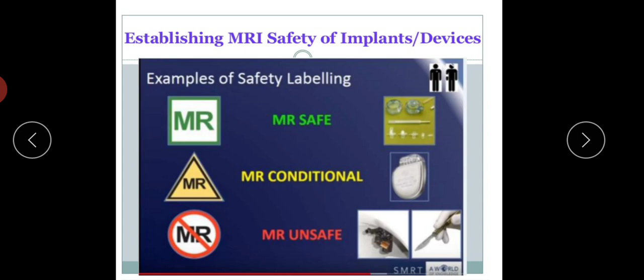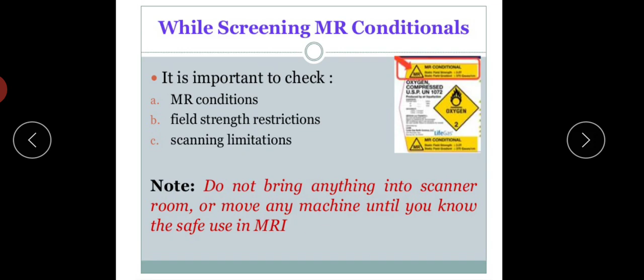Here are the safety labelings for MR safe, MR conditional, and MR unsafe. While screening MR conditionals, it is important to check MR conditions, field strength restrictions, and scanning limitations. Note: do not bring anything into the scanner room or move any machine until you know the safe use in MRI.